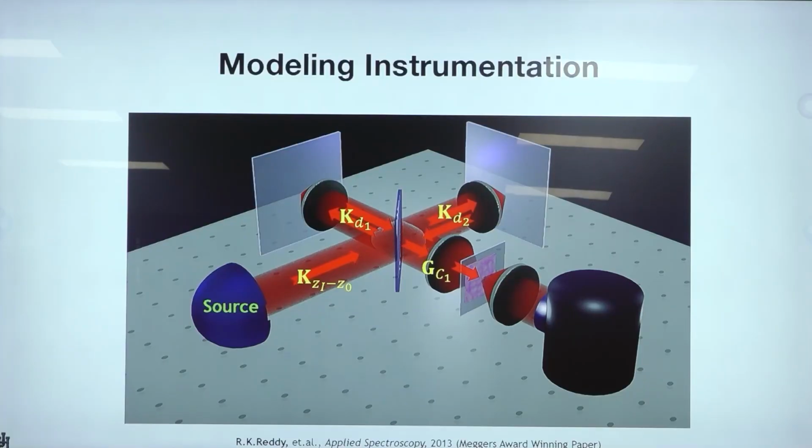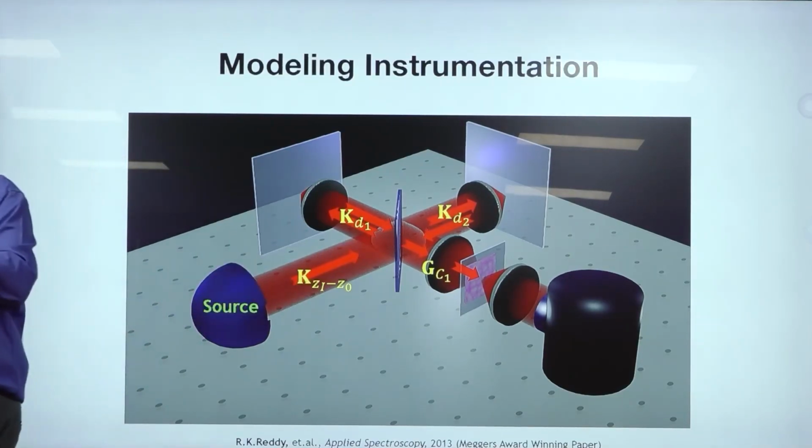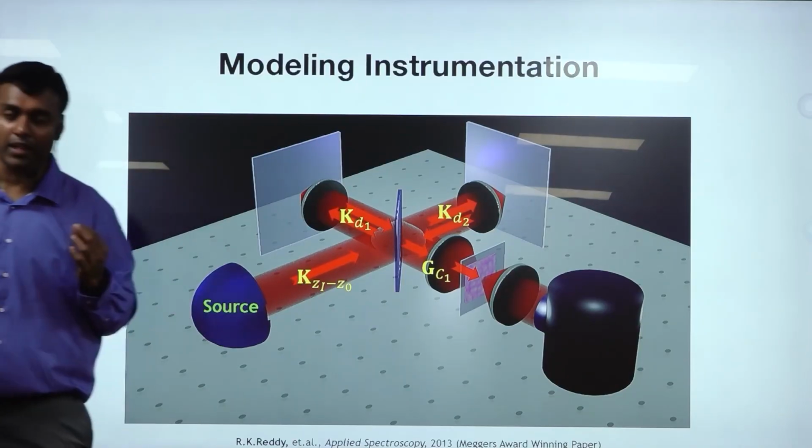So when there is a large range of wavelengths in an optical system, all wavelengths have to be focused on the same spot, which is really hard to do with a lens. So in that kind of situation, instead of a lens, you use a pair of mirrors. The advantage of mirrors is that the angle of incidence is equal to the angle of reflection, no matter what the wavelength is. So all wavelengths travel the same path, and you can use a pair of mirrors for focusing. That's called a Schwarzschild Cassegrain.